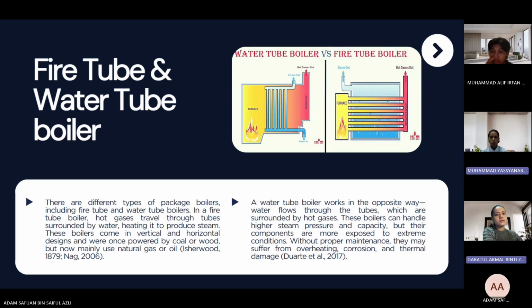Water flows through the tubes, which are surrounded by hot gases. These boilers can handle higher steam pressure and capacity, but their components are more exposed to extreme conditions. Without proper maintenance, they may suffer from overheating, corrosion, and thermal damage.